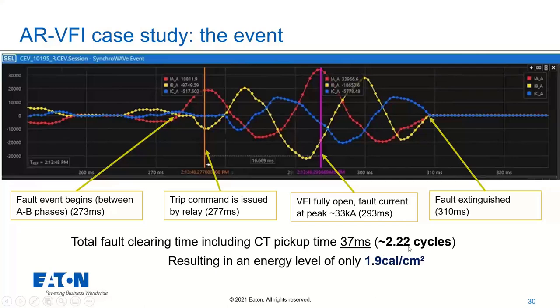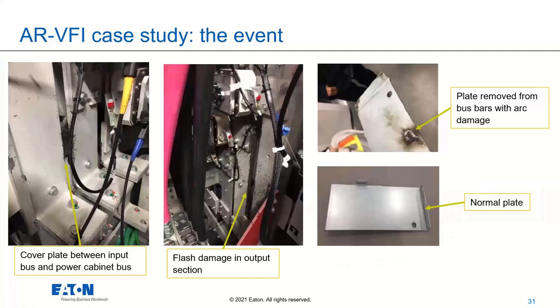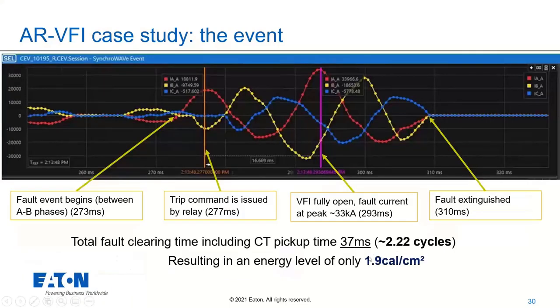I will divulge that in this instance, there was a maintenance mode activated. So this was a case where they were doing the startup and they did have that extra level of protection. But even still, had you not had maintenance mode, the calculations would show that this is still only about 4.8 calories in that case. So still extremely low because of this integrated secondary sensing.